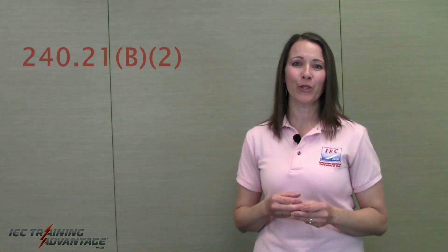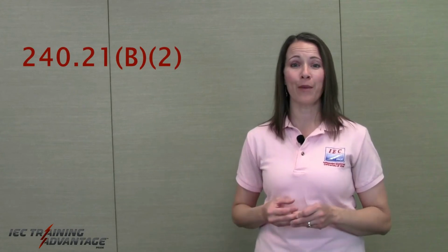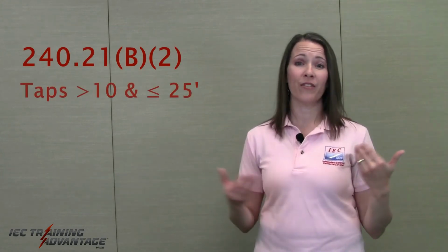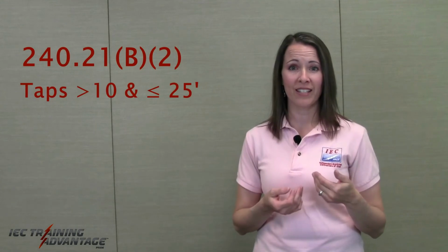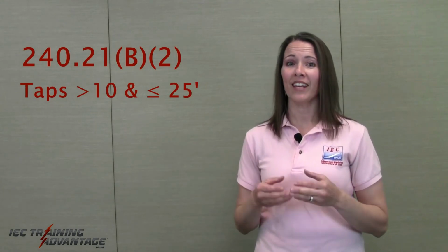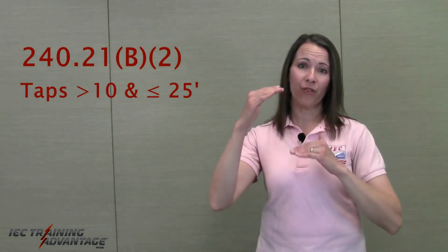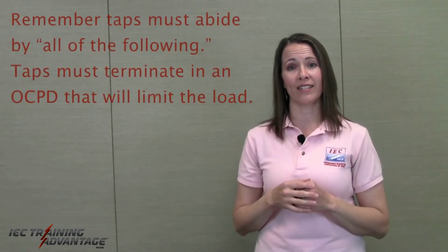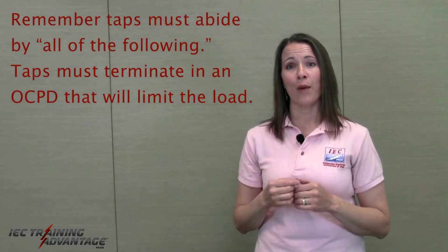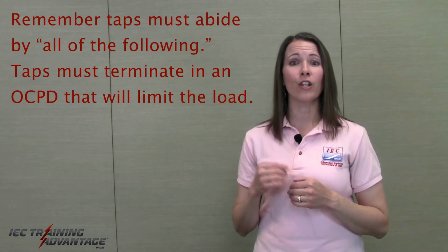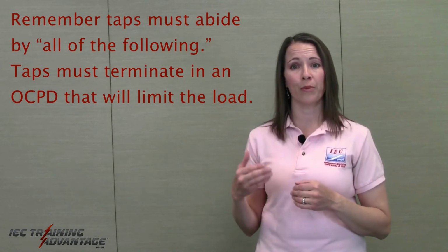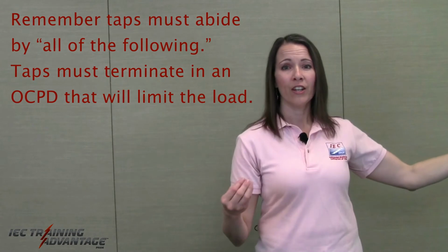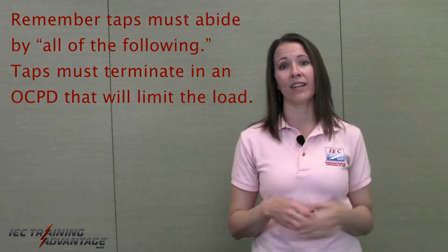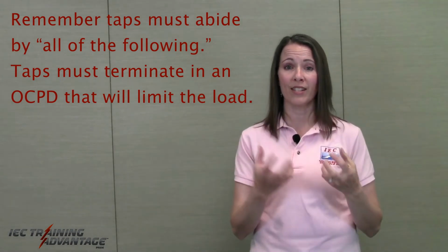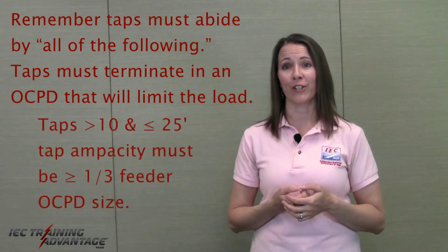Next, 240.21(B)(2). This is for taps that are over 10 feet and less than 25 feet. Again, it has a rule that you have to follow all of the criteria listed in that section. Taps must terminate in a load-limiting overcurrent protection device. So after you string your taps out, you have to terminate in some kind of protection that's going to limit the load to that conductor.